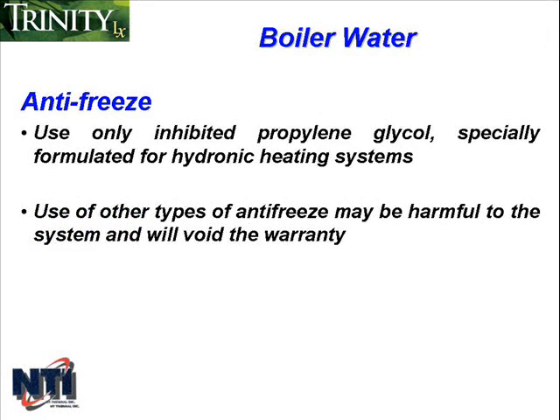For systems requiring freeze protection, you should only use inhibited propylene glycol, specially formulated for hydronic heating systems. Don't use other types of antifreeze as they may be harmful to the system. And it's important to remember that using glycol could reduce the usable output capacity of the boiler, requiring the unit to be downfired by limiting the maximum operating capacity and/or the maximum water temperature. NTI recommends against exceeding 35% concentration of glycol.